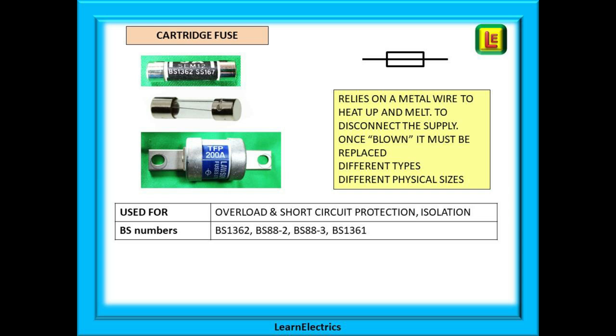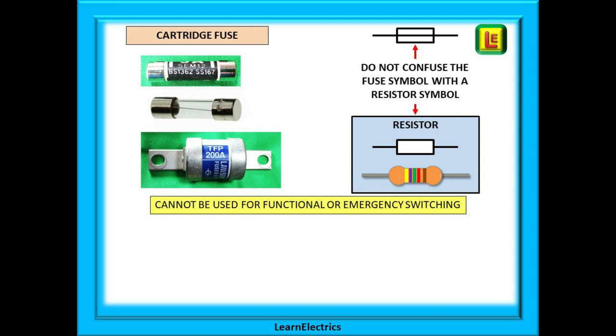Fuses can be used for overload and short circuit protection, and by removing the fuse they can also be used for isolation of the circuit. However, because it takes time to find a screwdriver or spanner to remove a fuse, they cannot be used for emergency switching or everyday on-off switching — what we call functional switching. Lastly, do not confuse the symbol for a fuse with that of a resistor as they do look a little similar.